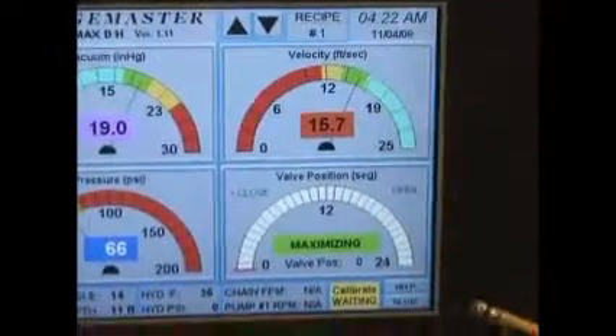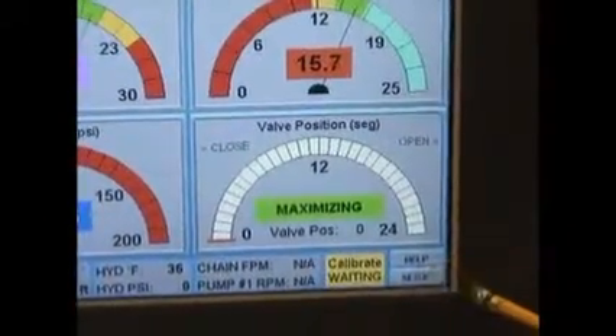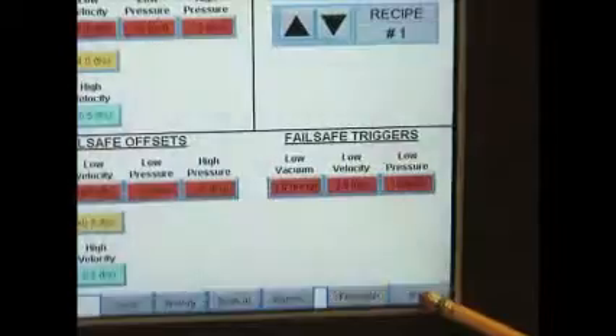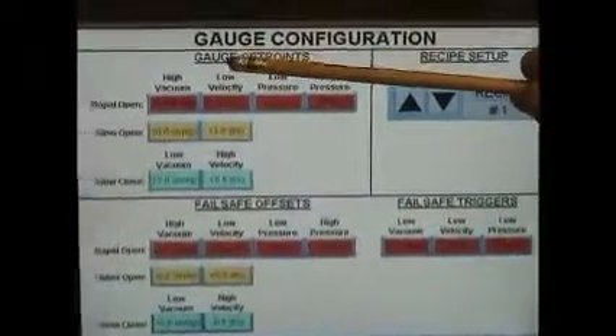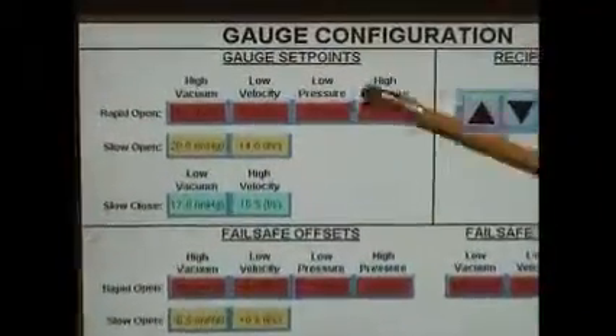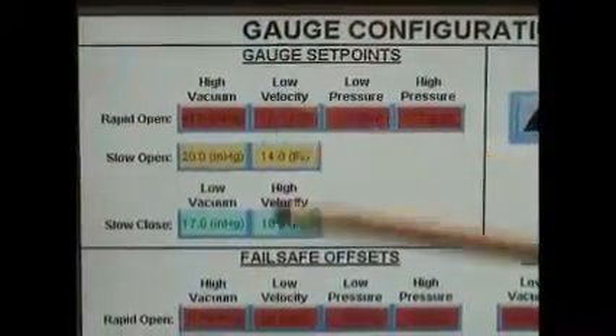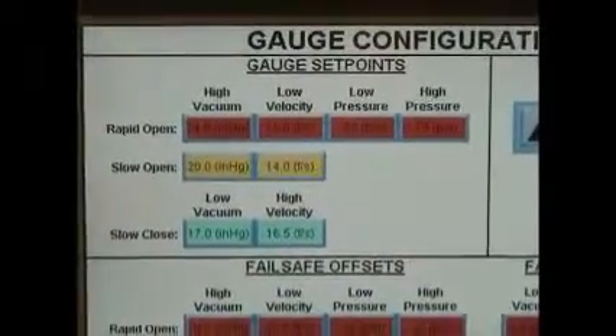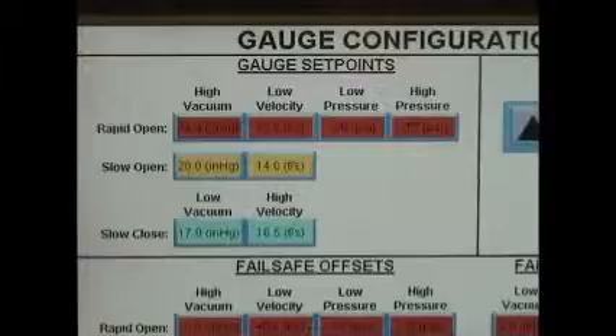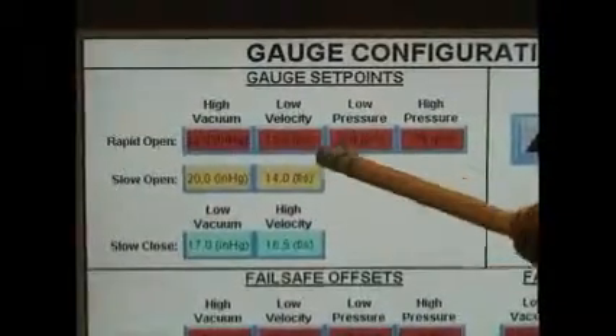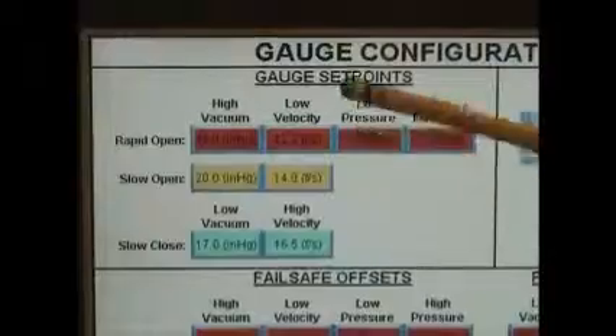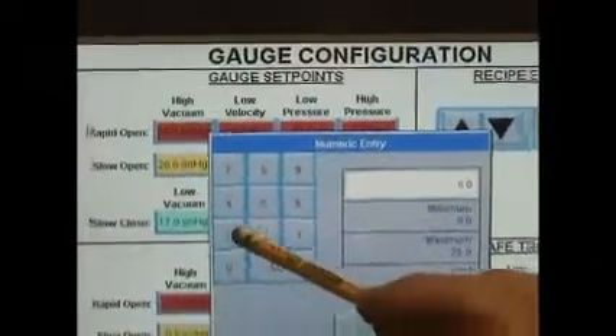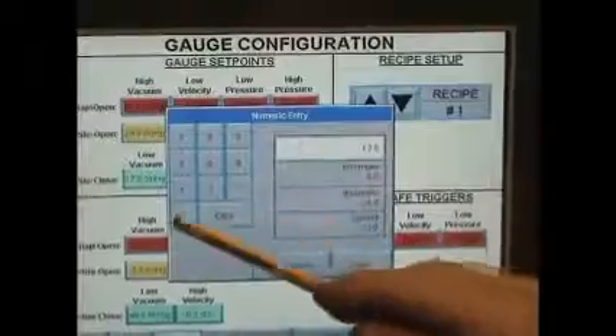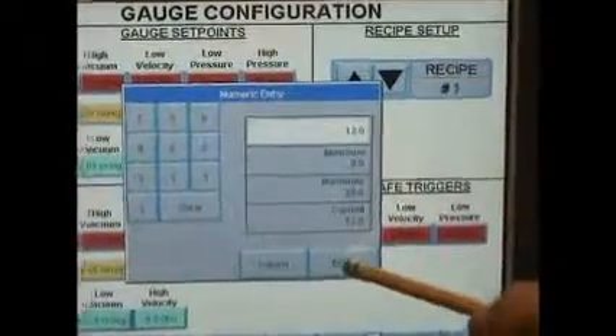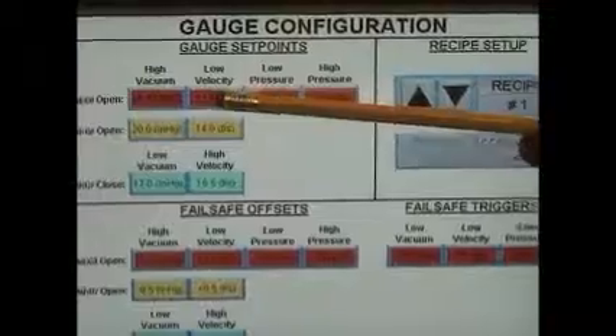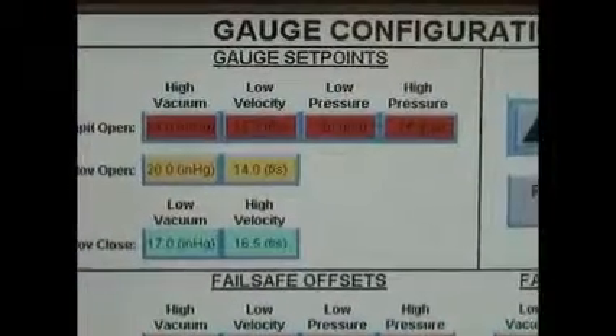Okay, we're going to show you in the setup screen how to change your velocity parameters. First thing you do is touch your little setup button in the lower right hand corner. We now have our low velocity set points. Our rapid open is currently set at 12 feet per second, or could be meters per second. If we want to change that, let's say we want our valve to rapidly open at 13 instead of 12, we're going to enter in 130 to give us 13. Hit enter. The valve will now start to rapidly open at 13 feet or meters per second.